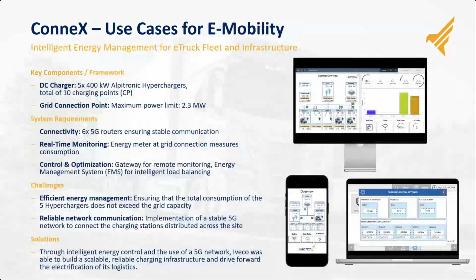The last slide is about another use case, a different one: pure load management. In this case, a company installed 5 Alpitronic DC chargers of 400 kilowatts. They have a building, and what they wanted to do is avoid consuming more than 2.3 megawatts from the grid. The challenge here was that each of the charging stations was far away and separately located.